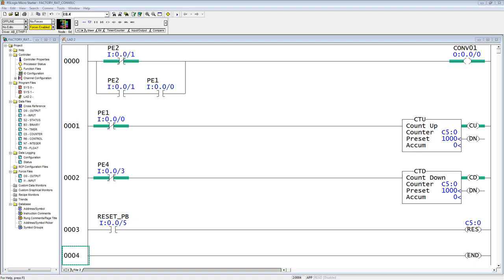So when you look at rungs 1 and 2, you see that when the photo-eye goes from on to off, or you could say this instruction goes from false to true, then it either counts up or counts down. Counts up at photo-eye 1 when they clear photo-eye 1 onto the conveyor, and when they clear photo-eye 4 onto the next conveyor, it counts them down off.